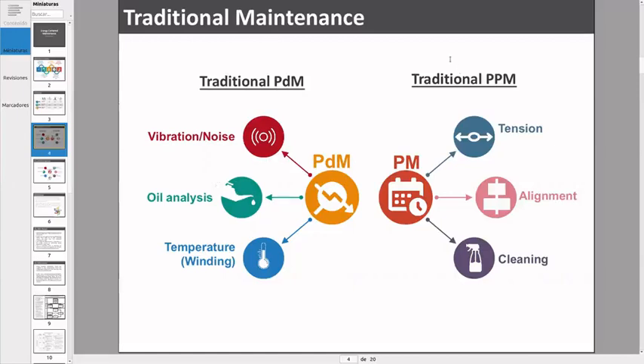We'll talk about setting the ground for an air handling unit, for example. In normal planned preventive maintenance, we do tension for the belt. The fan has a belt, it might be loose, so we do that kind of tension. If we find that the shaft for the fan is not aligned, we do some alignment for it. We could do cleaning for the coil, cleaning for the strainers, replacing the filters, and maybe lubrication for the motors and the bearings.